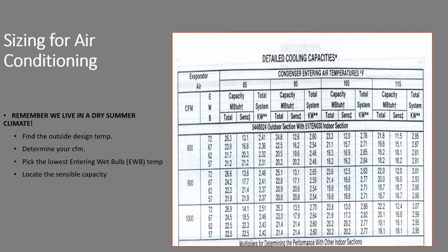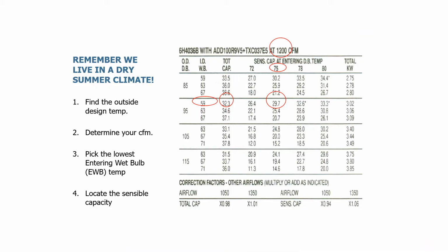And then you locate the sensible capacity. And this manufacturer showed sensible capacity in a different table. So please notice here at 72 degrees entering wet bulb, the sensible capacity is only 13,000 BTUs per hour. The total capacity is 26,000 BTUs per hour. The difference is all tied up in latent capacity, in removing and turning that humid, muggy air in the form of vapor into water. Boy, at a 62 degree entering wet bulb, it's almost identical. By the time you get down to 57, it is identical, meaning the capacity of that machine is all sensible and it's available to lower the temperature of the air as it goes through the coil.